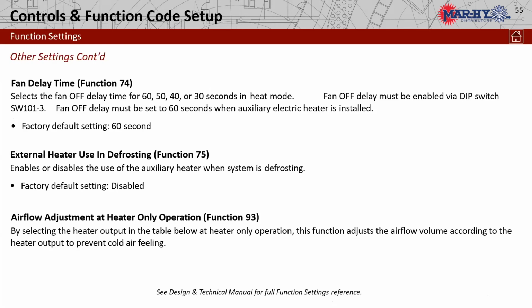Fan time delay. Remember, we already set the dip switch on the indoor unit because we know we're going to be using strip heaters. We switched on the fan off delay, and from function 74, we'll set the seconds of time delay that we want. Now, mind you, if there is strip heat installed, we want it set for 60 seconds. Factory default is 60 seconds. So you won't make a change on that. You just got to make sure you flip that dip switch in that air handler so that it will give us that fan time delay off.